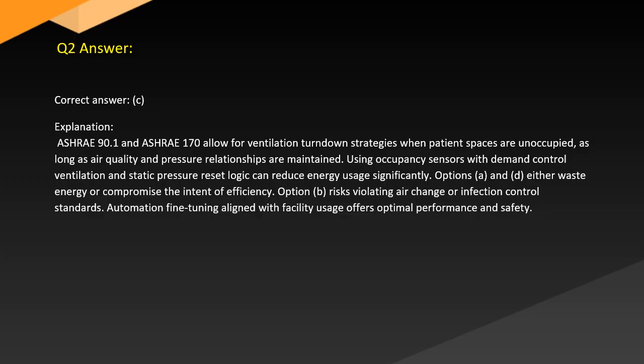ASHRAE 90.1 and ASHRAE 170 allow for ventilation turndown strategies when patient spaces are unoccupied, as long as air quality and pressure relationships are maintained. Using occupancy sensors with demand control ventilation and static pressure reset logic can reduce energy usage significantly. Options A and D either waste energy or compromise the intent of efficiency. Option B risks violating air change or infection control standards. Automation fine-tuning aligned with facility usage offers optimal performance and safety.